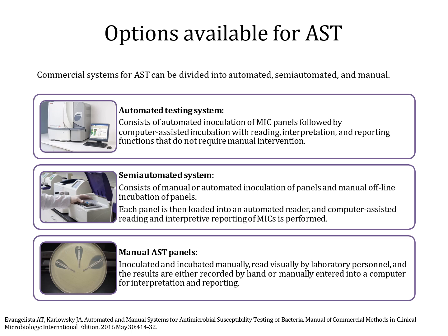In automated systems, this consists of automated inoculation of the MIC panels followed by computer-assisted incubation with reading, interpretation, and reporting functions that do not require any manual intervention. In semi-automated systems, it consists of manual as well as automated steps. Each panel is loaded into an automated reader and computer-assisted reading and interpretation of MIC is performed. In manual AST, the antibiotic discs are incubated manually, the zones of clearing are read visually by lab personnel, and the results are entered by hand into the computer for interpretation and reporting.